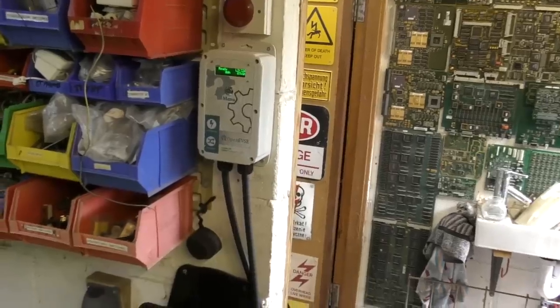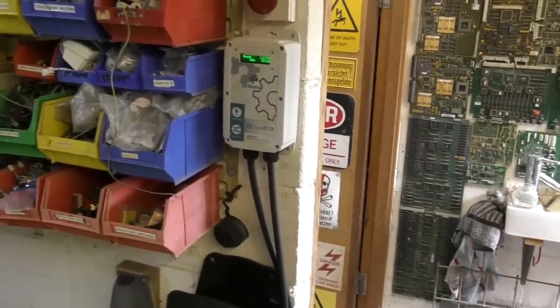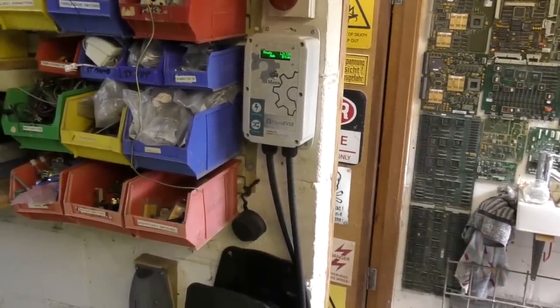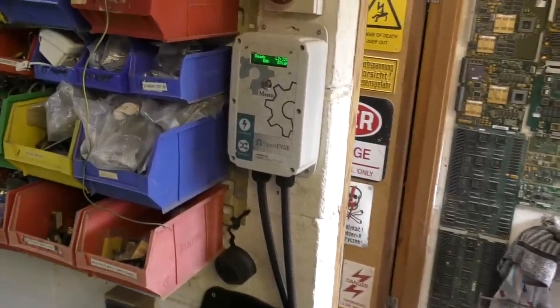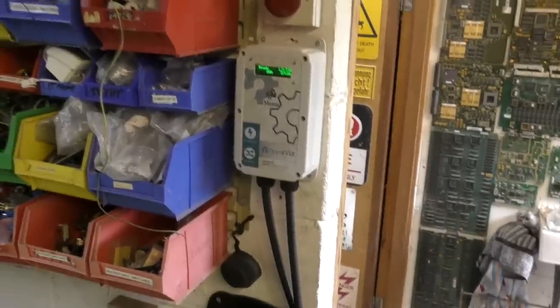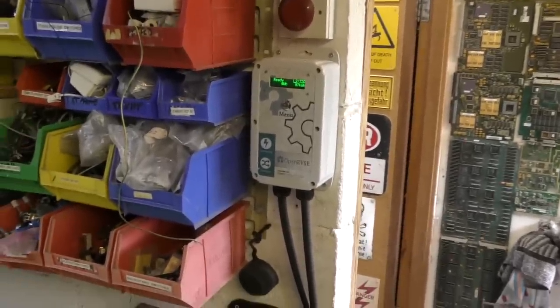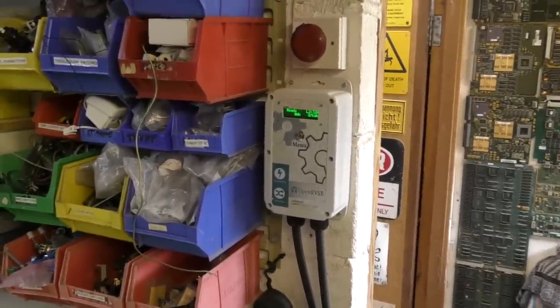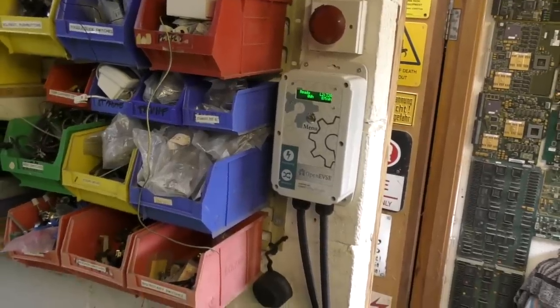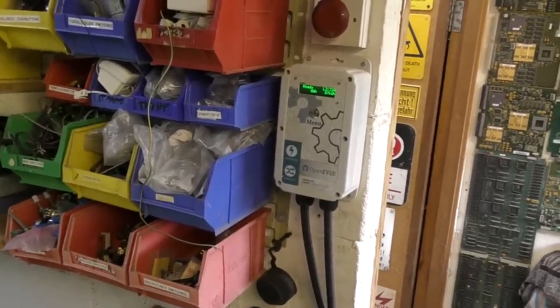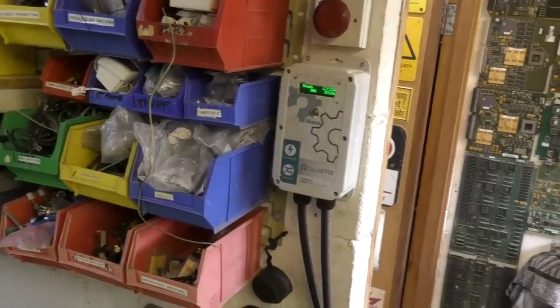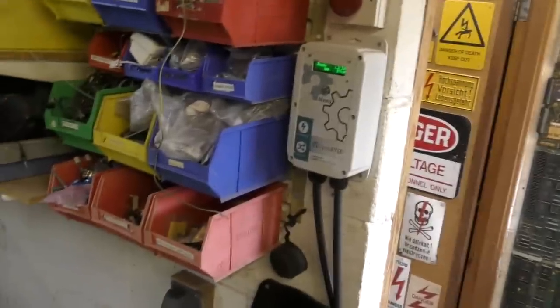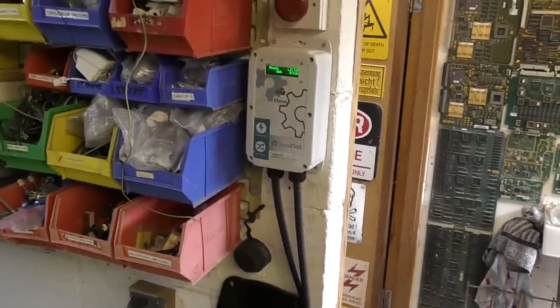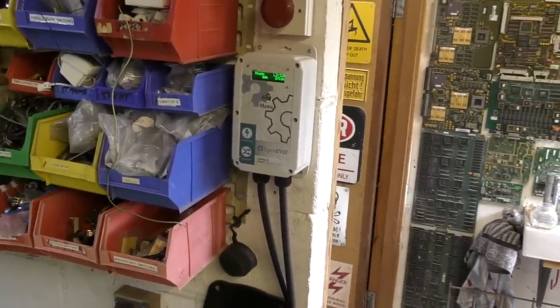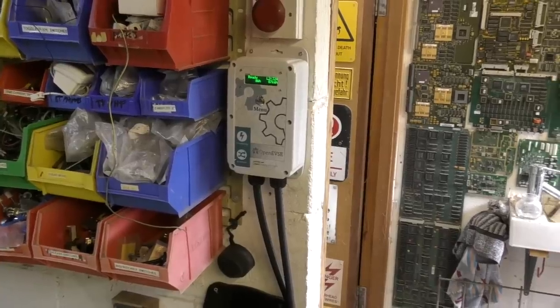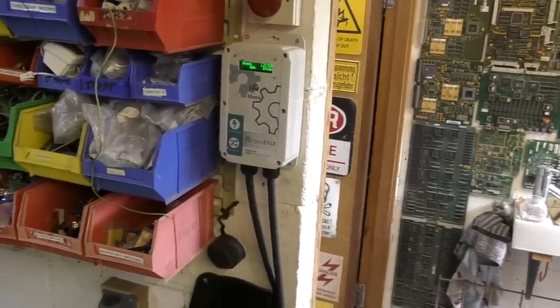The second option is a level 2 charger. These are typically 32 amp, 7 kilowatts, and they're usually hardwired into a dedicated circuit on the house distribution board. There's quite a few of these available, and in the UK there's actually a grant available to subsidise the cost. And I think partly for that reason the cost of these is quite expensive. The complete cost including installation typically in the UK is of the order of £750 to £1,000, but there's a £500 grant that reduces that to £250 to £500, and there's various levels of sophistication.